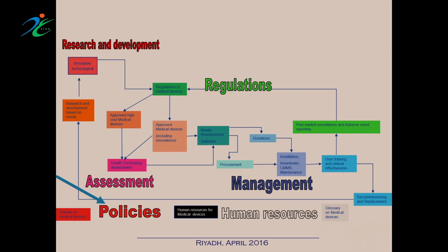And then you have the installation, and you see the linkage between the HTM and the regulations. After installation and commissioning, you ensure that user training is done, and any adverse incidents that take place are reported back, so that the regulation can tackle those issues through post-market surveillance and ensure that whatever equipment is on the market is of high quality, and the risk coming from those equipment is minimized.